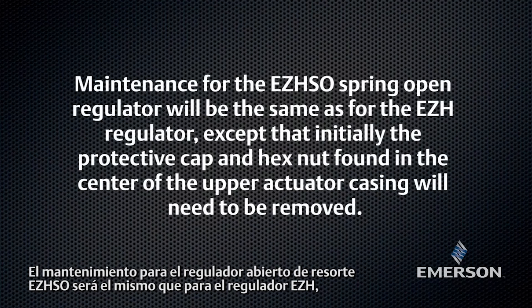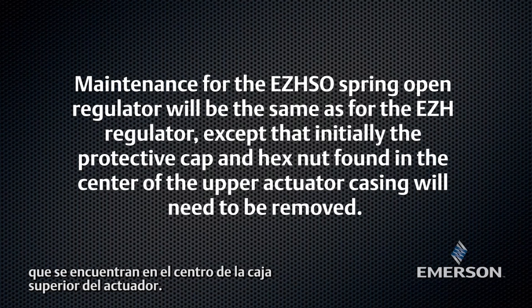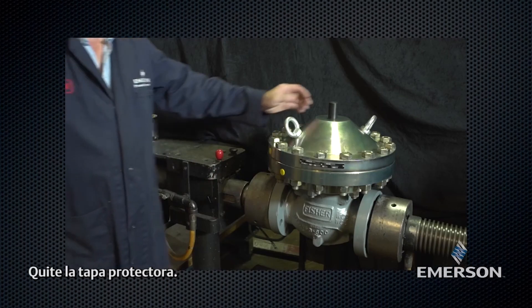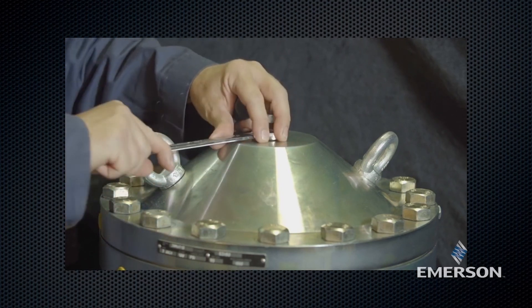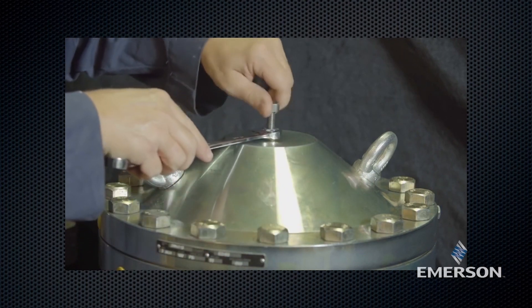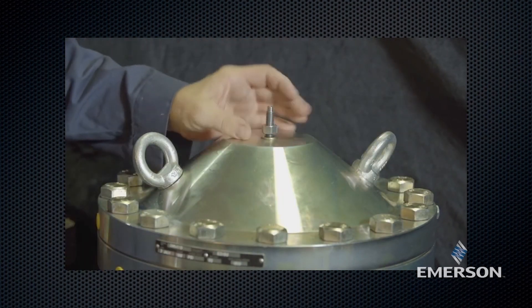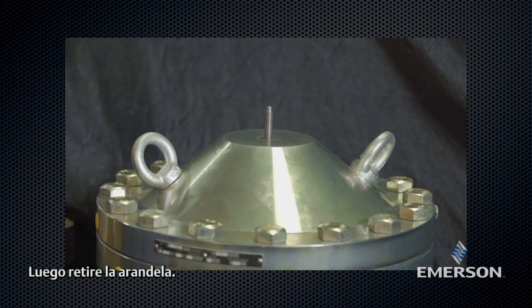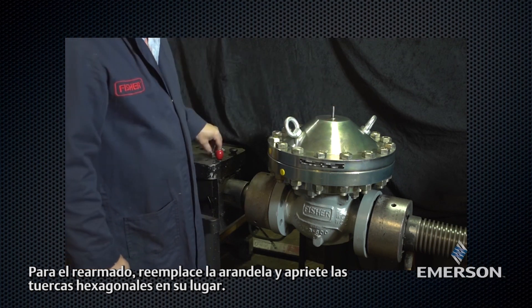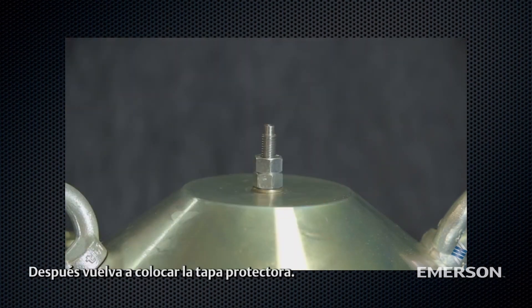Maintenance for the EZH-SO spring open regulator will be the same as for the EZH regulator, except that initially the protective cap and hex nut found in the center of the upper actuator casing will need to be removed. Remove the protective cap, then remove the hex nut. For reassembly, replace the washer and tighten the hex nut in place, then reinstall the protective cap.